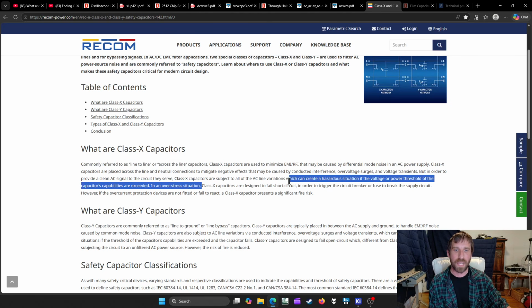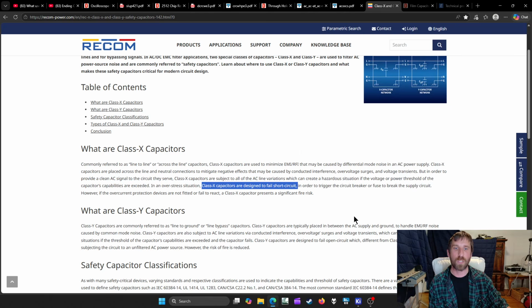We can read a little bit of this here, but point being, commonly called line-to-line or across-the-line capacitors. Important part: they are designed to fail short circuit in order to trigger the circuit breaker or fuse to break the supply circuit. So this is a safety thing, we got to do it.